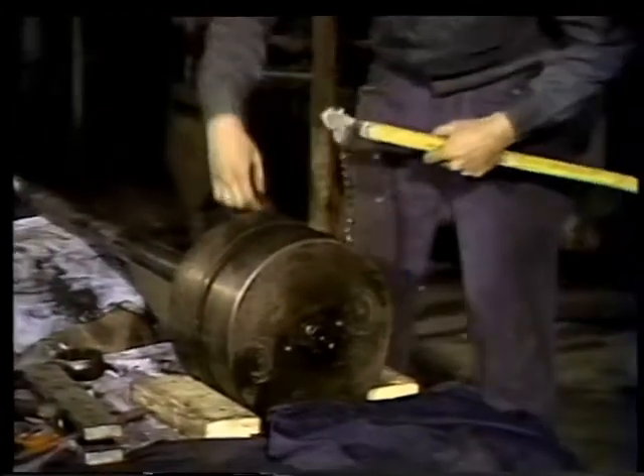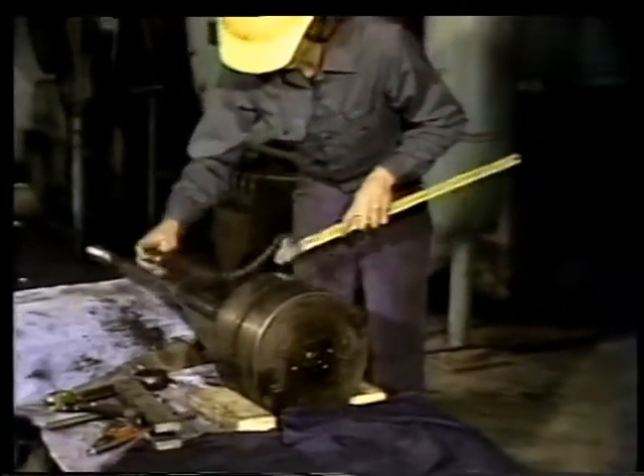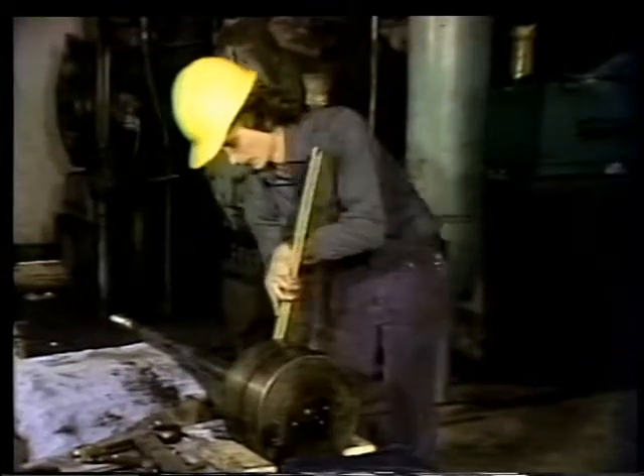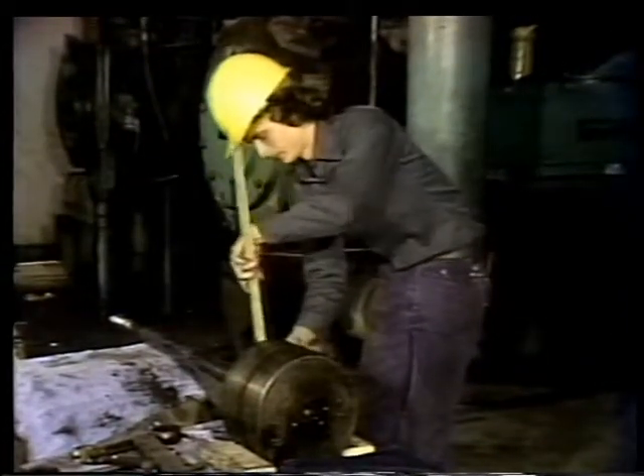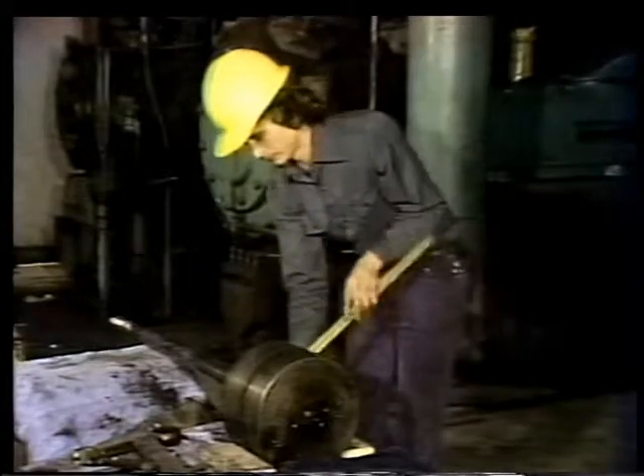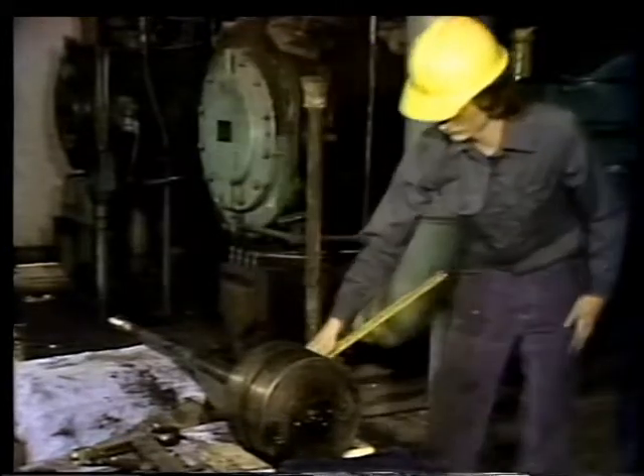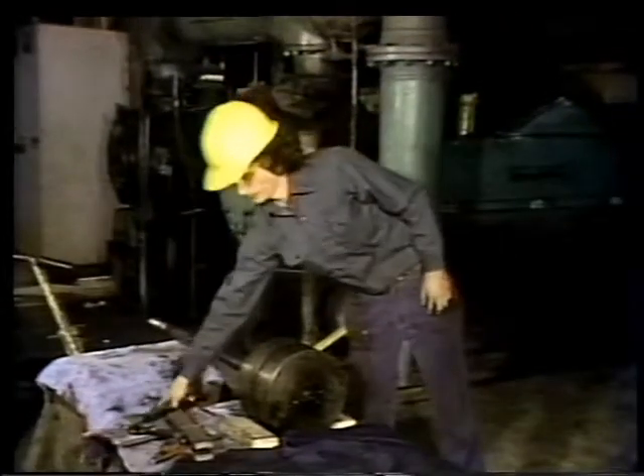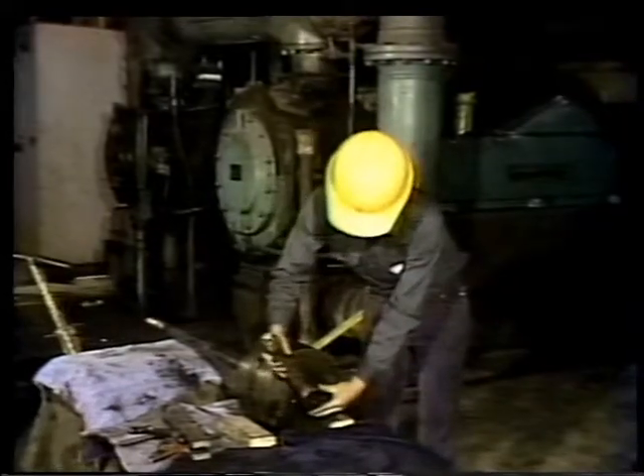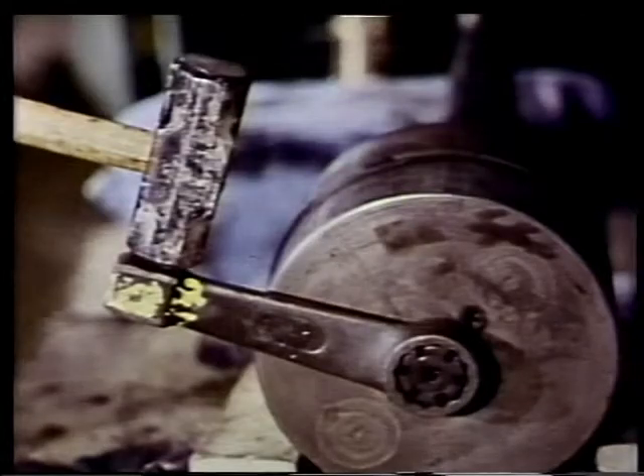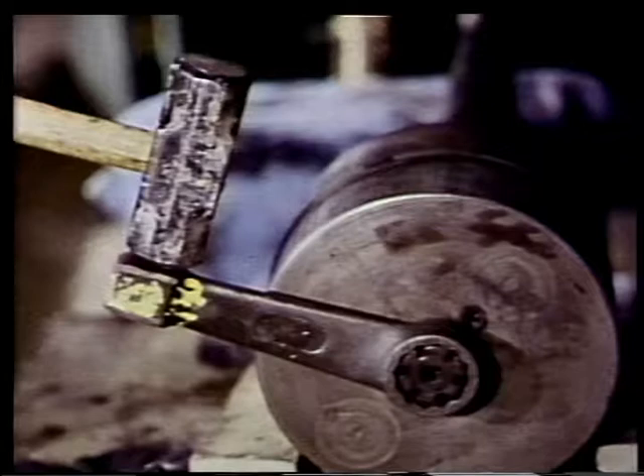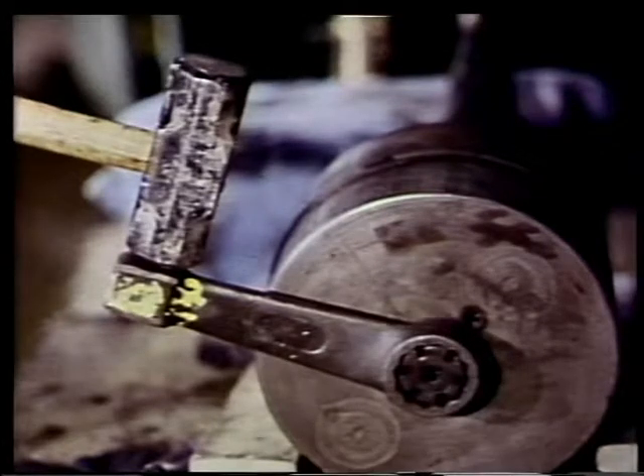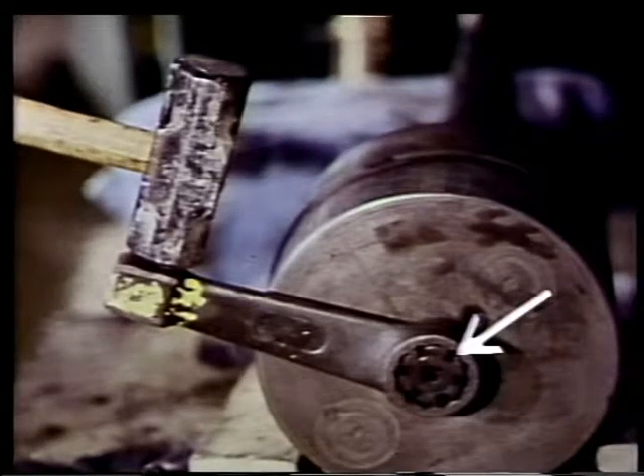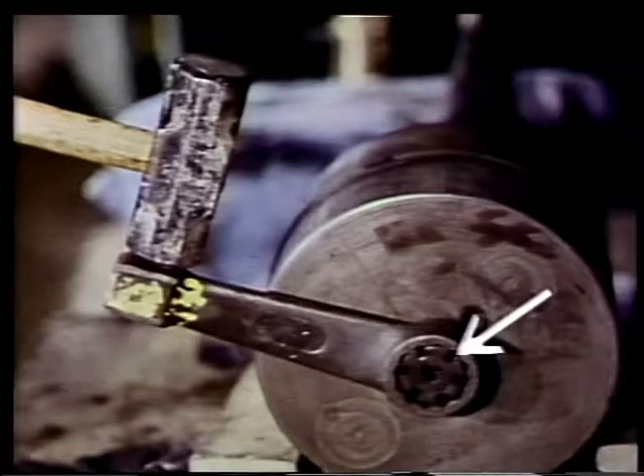It's okay to use a chain wrench to hold this rod because it's damaged and needs to be replaced. But if the rod was in good shape, you'd use a strap wrench, for instance, to make sure that it didn't get scratched while you were taking it out. The chain wrench will keep the piston rod from turning. You need a striking wrench to remove the nut. Sometimes the nut's hard to remove because of carbon deposits. If this is the case, it helps to spray penetrating oil on the threads.